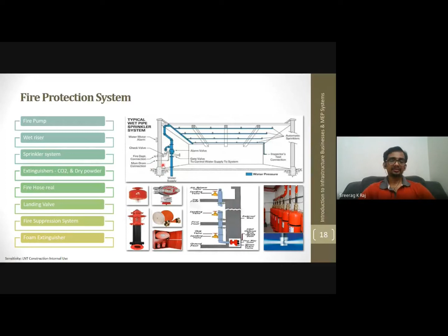Normally a building will have a water storage of say 2 or 3 hours of continuous operation. But in case the water is getting exhausted, we need a separate connection from outside. A water tanker or fire engine will come and connect through these fire hydrants to supply water inside the building. Normally this will be a dry riser, while the wet riser will have connectivity to the sprinkler.